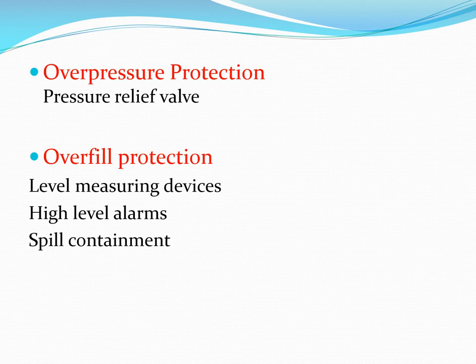Overfill protection for a pressure vessel should include instrumentation with two independent level measuring devices that can be repaired without removing the vessel from service. The vessel must also be provided with a high-level alarm independent of other level instruments. Spill containment consists of a dike to prevent the uncontrolled dispersal of flammable liquids; spills are confined inside the dike area and diverted away from the vessel, with the ground graded and sloped away from it.